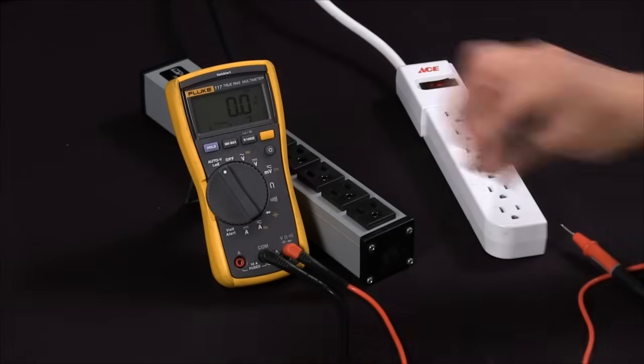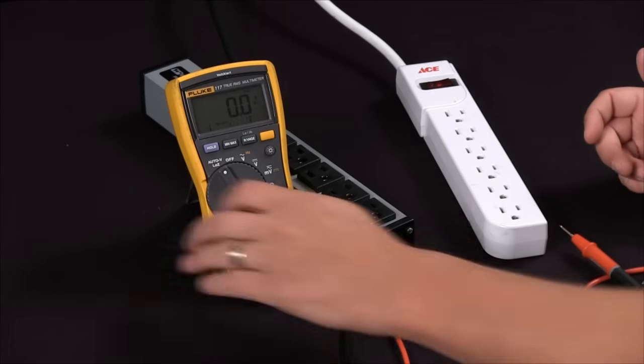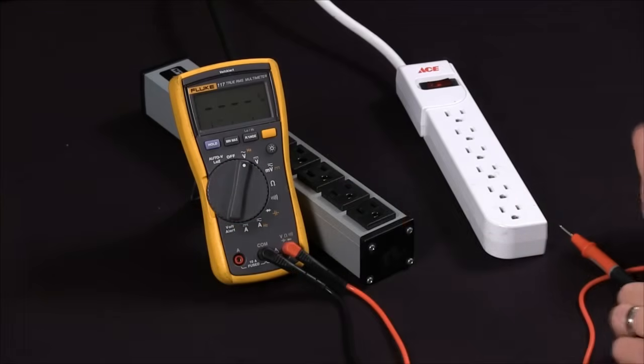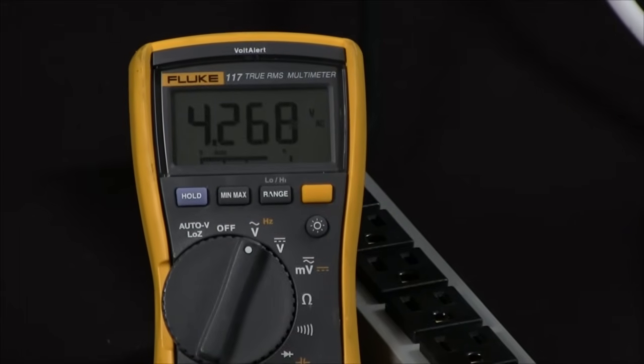In our second instance we're going to take a measurement with something that has an improper ground. We'll go back to our voltage setting, ground to hot, and you can see that I'm getting a low voltage reading.